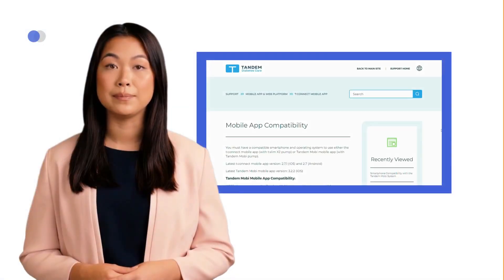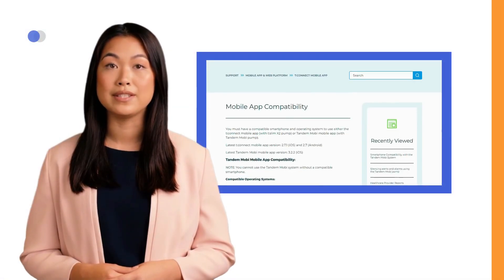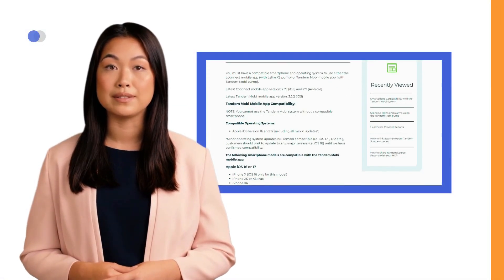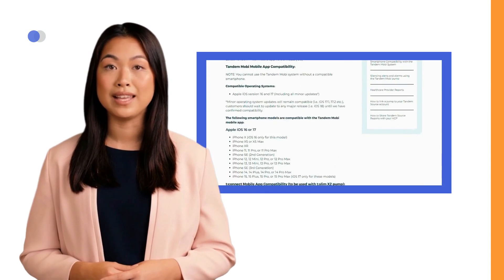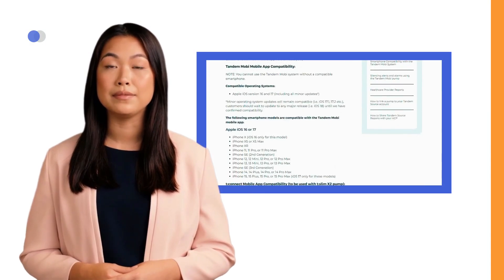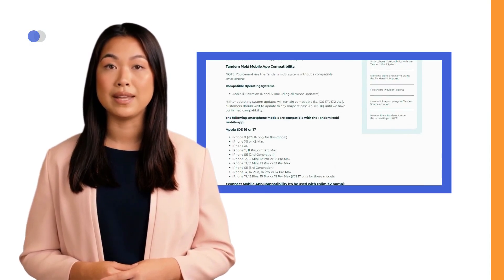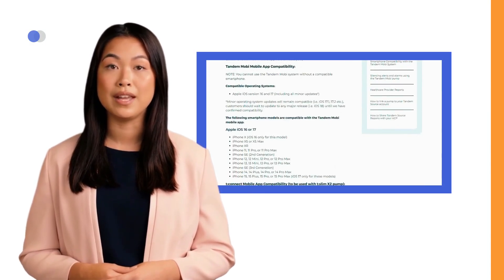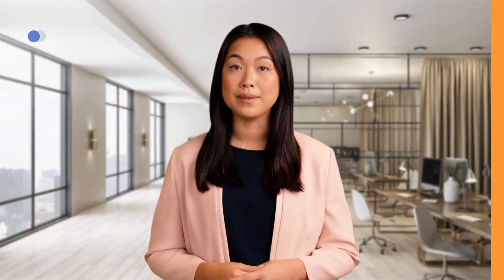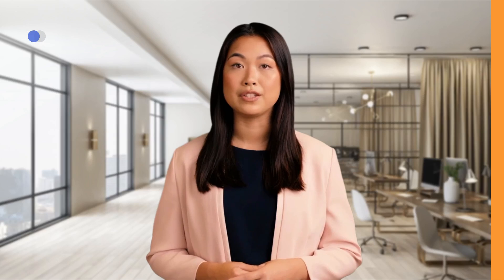The Tandem Mobi mobile app is only available for iPhones with iOS versions 16 and 17. You can check your device's compatibility on Tandem's website. The Tandem Mobi mobile app must run in the background in order to receive and transmit data to and from your pump, as well as to the Tandem cloud. Be sure to disable battery optimization on your smartphone to ensure the Tandem Mobi mobile app can receive alerts and alarms.